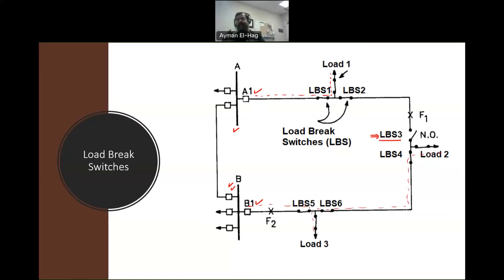Generally speaking, we design the distribution system as a ring system but operate it as a radial system. We design it as a ring from the beginning because if we close the normally open switch, we have the ability to feed loads from the other bus. This normally open switch is key to switching the system between ring design and radial operation.